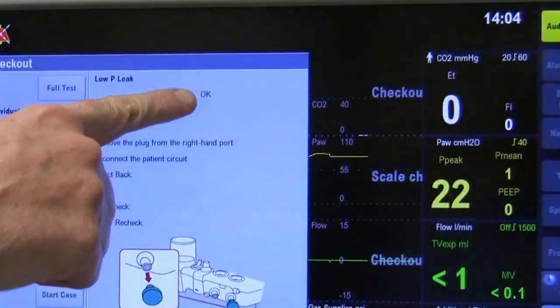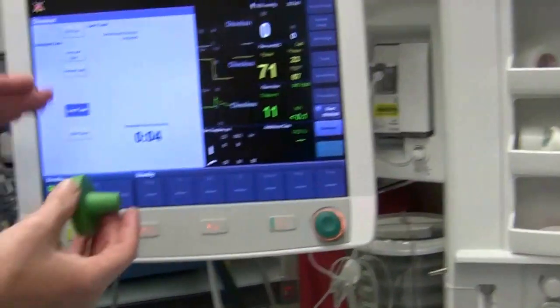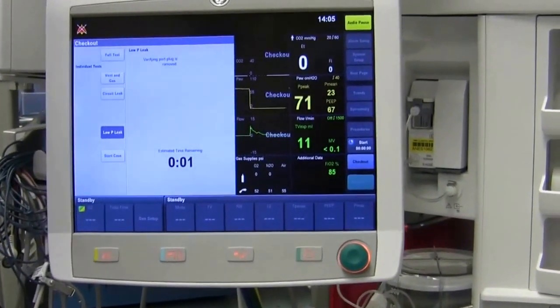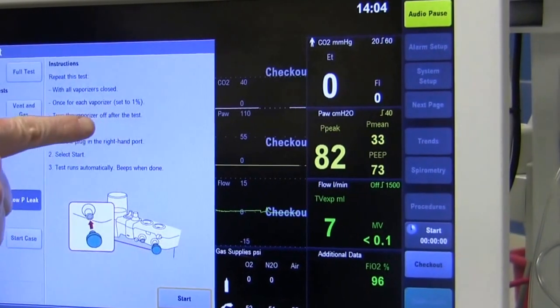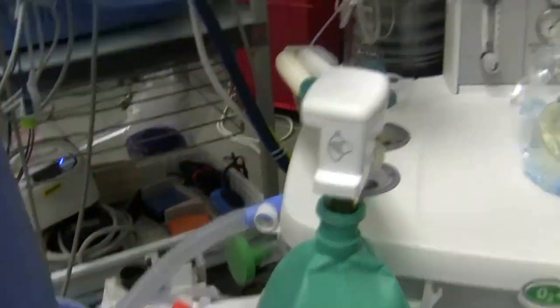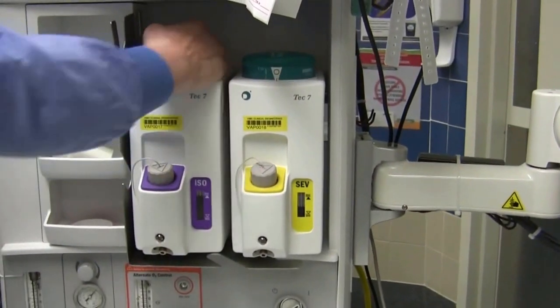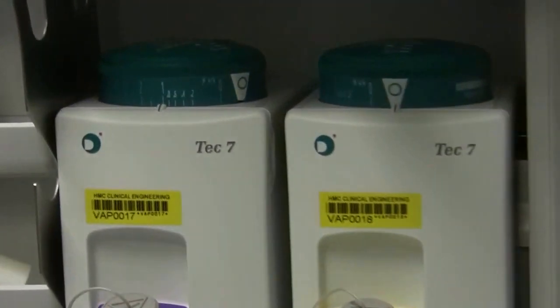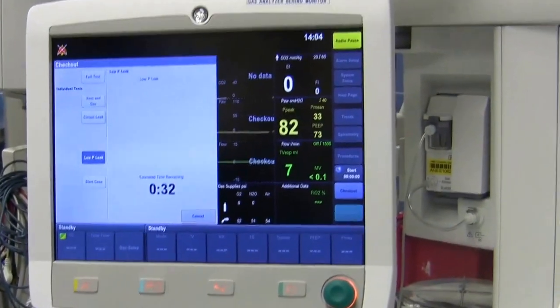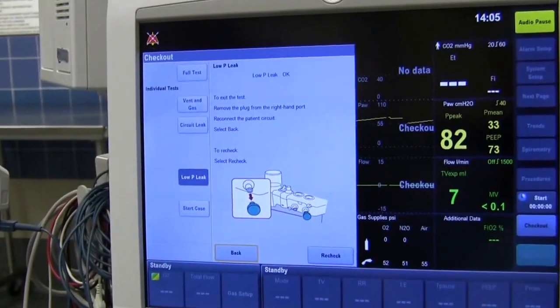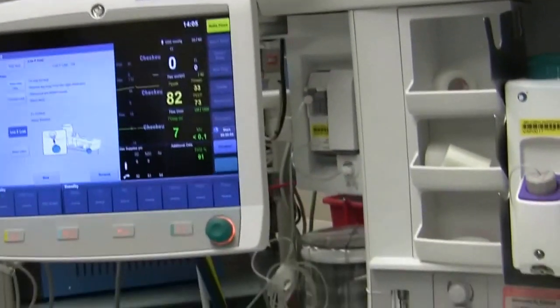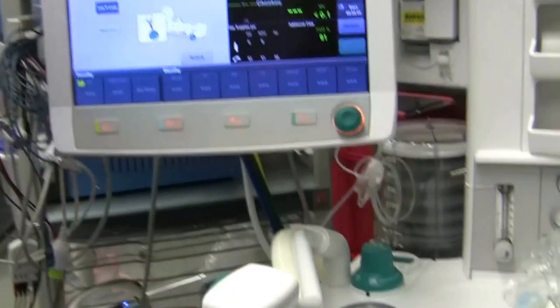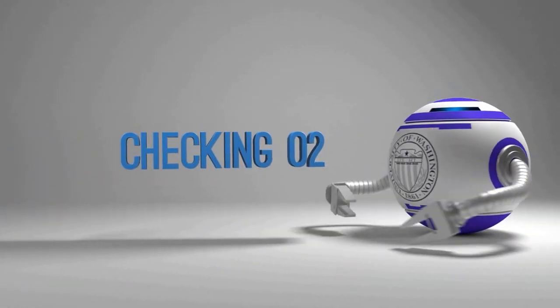Low leak test okay. It yells at you if you hit back before you take this plug out. It needs to confirm that you've taken the plug out. I hit the back button. I'm going to do the low pressure test again, and I'm going to put the plug in the same right port, and I'm going to put the vaporizer to 1%. And hit the start button again. And you'll do that for each of your vaporizers. Great, so that one's okay, and then you would proceed and do the exact same thing for the next one.